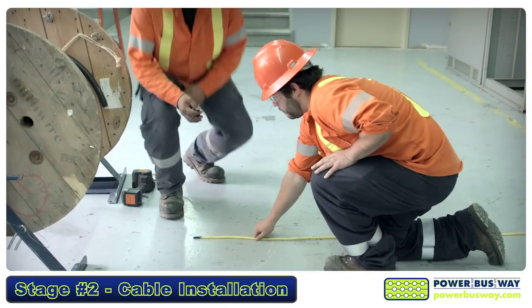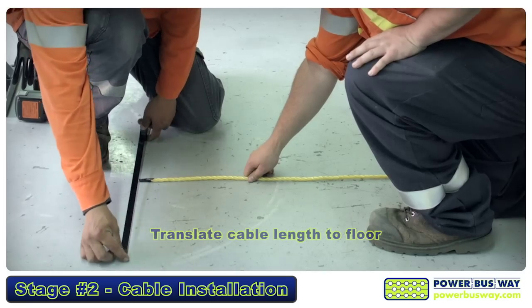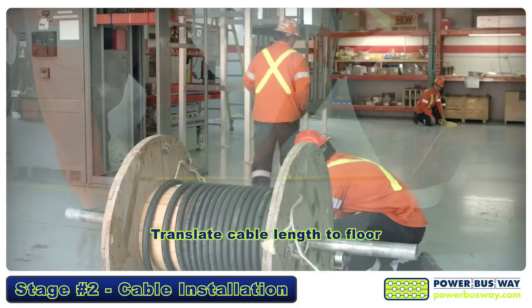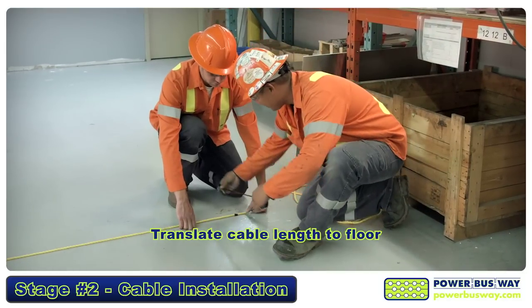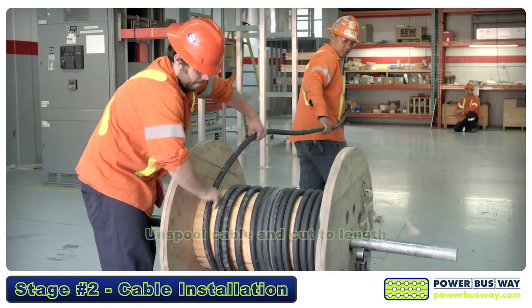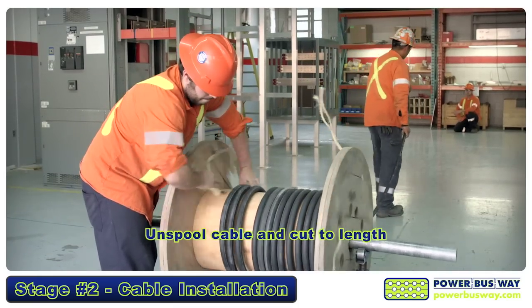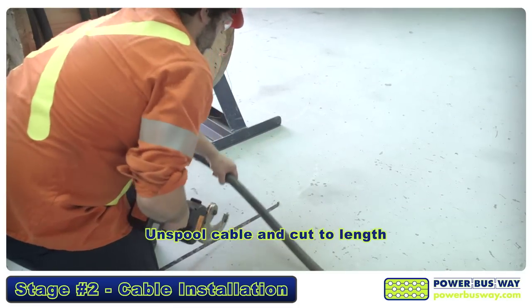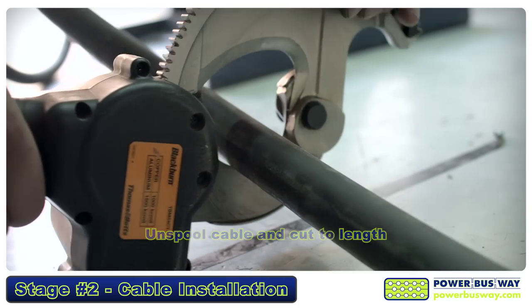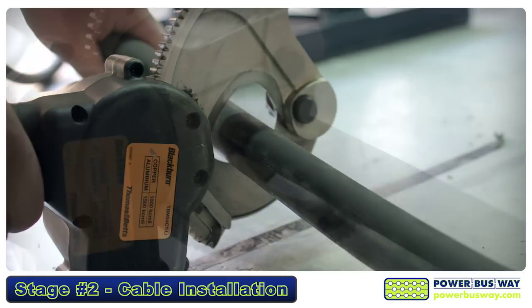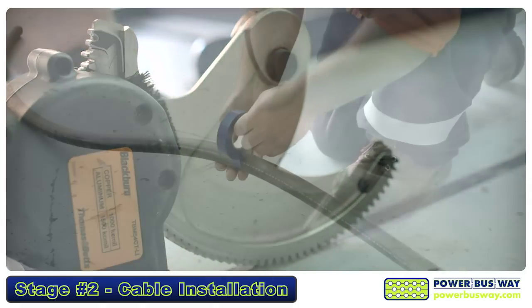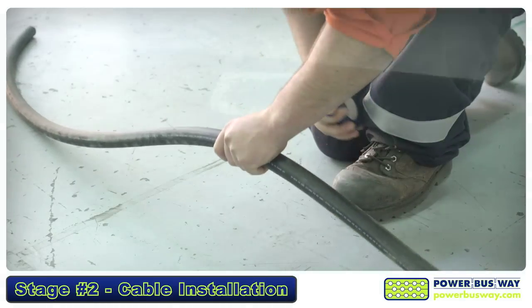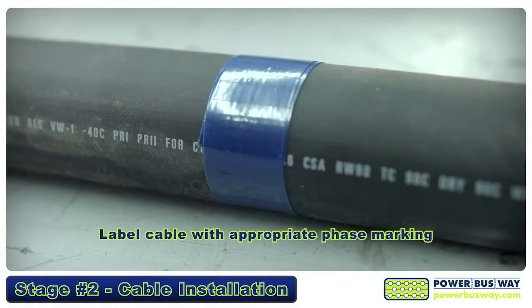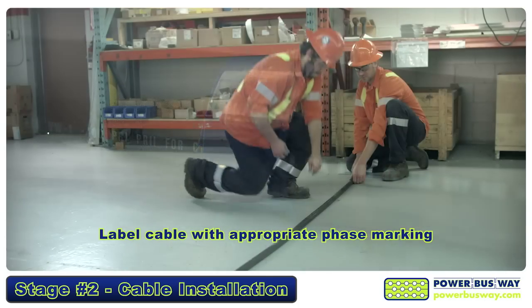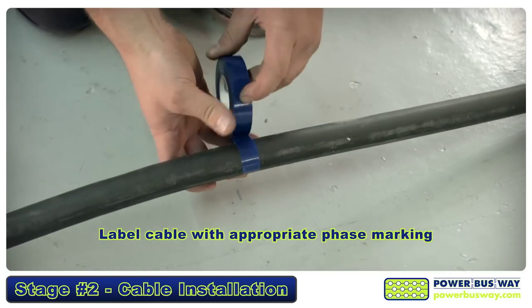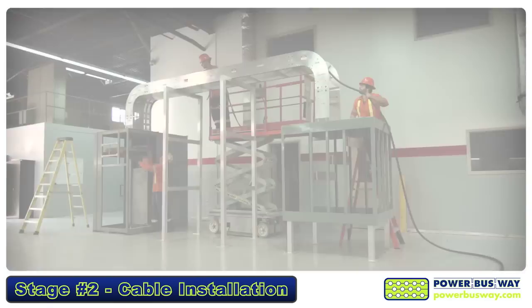At this point, you'll prepare an initial cable to verify your measurements. Translate the cable length to the floor just beyond your cable reel. Unspool a length of cable in accordance with the floor markings and cut using cable shears. Consult your installation drawings for phase arrangement and identify and label each cable at both ends with phase identification tape. The initial cable is now ready to be installed.